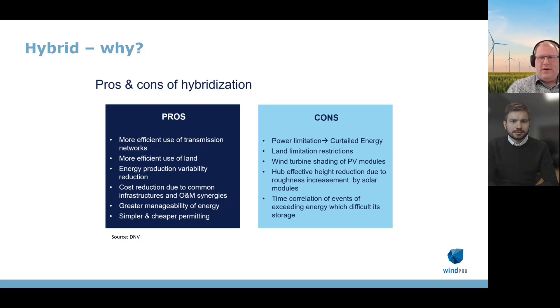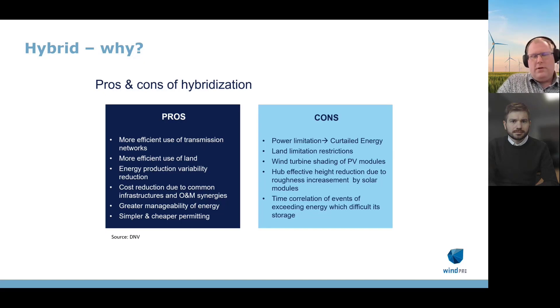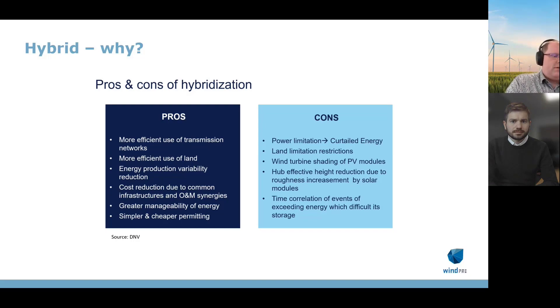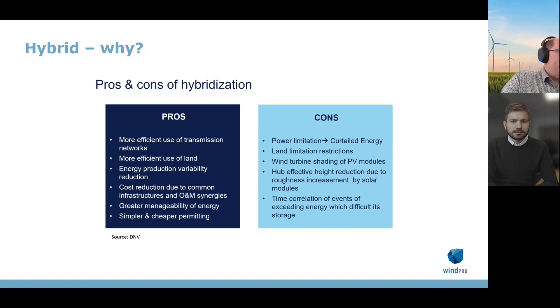What are the pros and cons of hybrid? The most obvious pro is, of course, the efficient use of transmission networks. You can combine a wind farm and a PV plant on the same grid connection. Taking Denmark as an example, you can install one megawatt of wind and one megawatt of PV and still only need one megawatt of grid connection — a one-to-one-to-one ratio. That means for one grid connection you can actually build a lot of installed capacity. You can also use the land more efficiently.